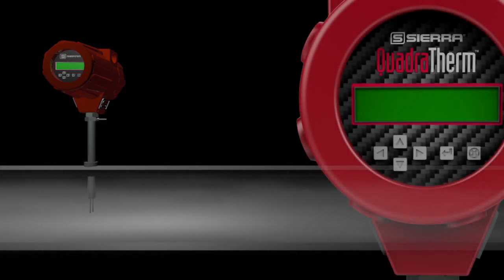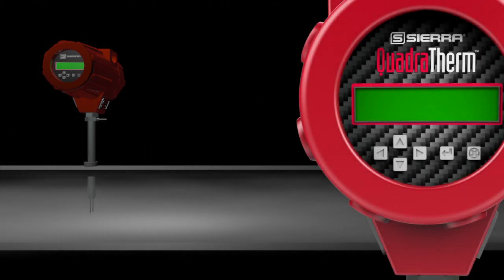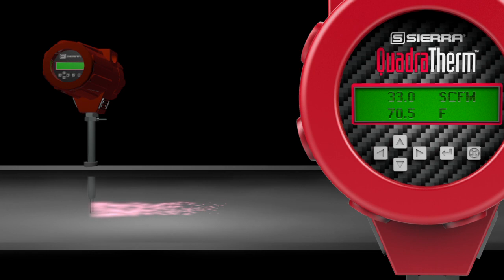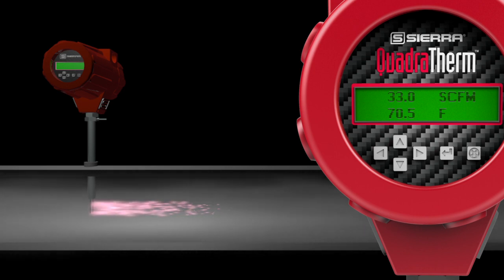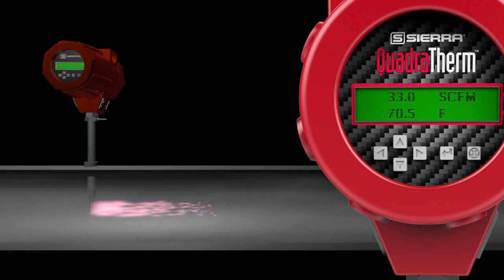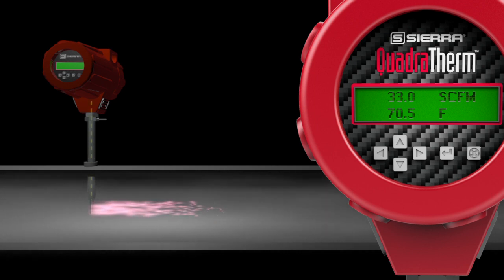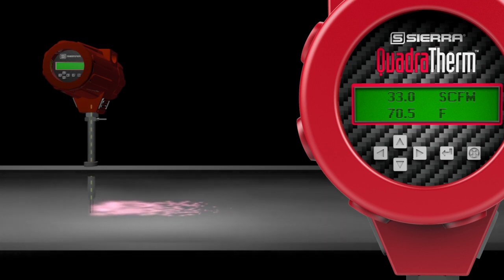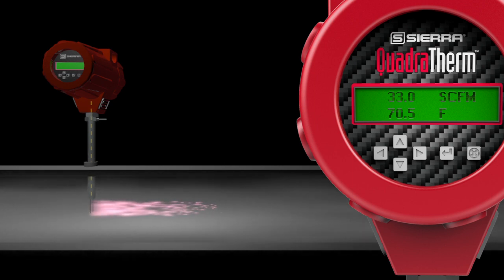Now, let's take another look at a cutaway view of a pipe with gas flowing through it. We have animated the molecular heat dispersion or cooling effect across the sensor that is occurring. You can see from the meter display on the right, the gas flow is 33.0 standard cubic feet per minute. The yellow dotted line represents the heating current sent to the sensor by the meter electronics.